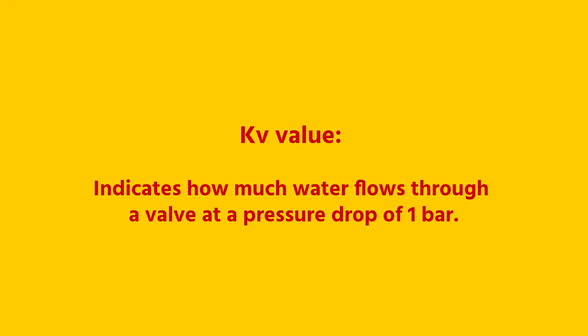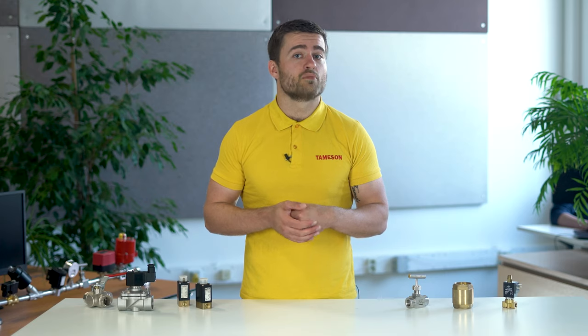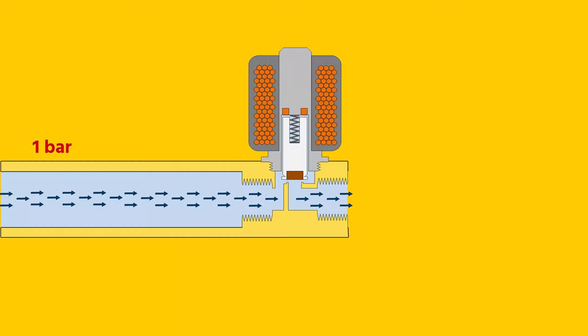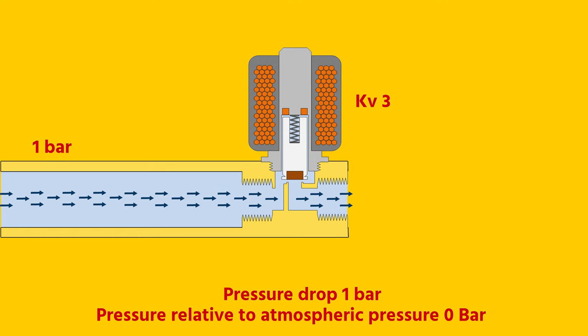The KV value indicates how much water flows through the valve at a pressure drop of 1 bar, indicated in cubic meters per hour, but can easily be converted to liters per minute. For example, suppose you have a water pipe with a pressure of 1 bar. At the end of the pipe is a valve connected with a KV value of 3. The pressure drop is then 1 bar because the valve is connected to the outside air, so the pressure relative to the atmospheric pressure is 0. The KV value of 3 means that the liquid flow through the valve will be 3 cubic meters per hour.